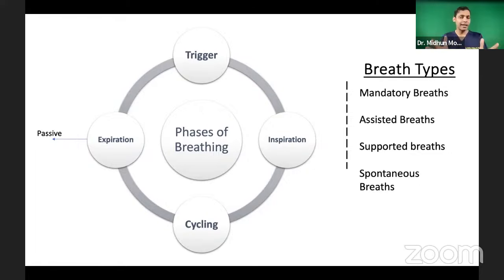Now, how these breaths differ is by knowing who controls which parameter in breathing. For that, we can divide the breathing into four phases. One is the trigger, then the inspiration part, then cycling, and finally the expiration part. Let's leave the expiration part because it's passive. The ventilator can only give the breath. It cannot help the patient to expire. Expiration is still a passive process caused by the elastic recoil of the lung.